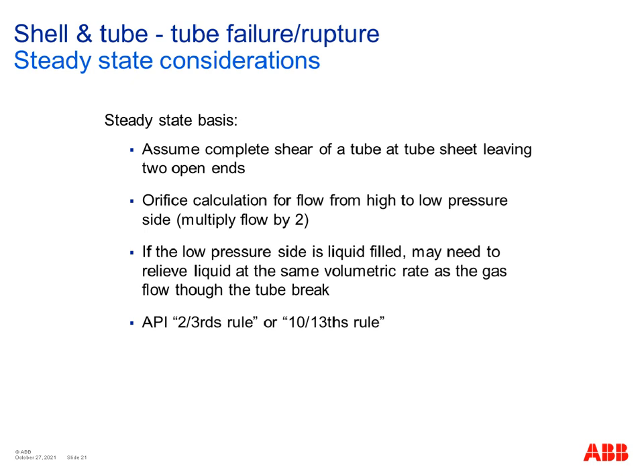So you've got a stub at the tube sheet, and then you've got flow coming out from that, and then you've also got the end of the tube that's broken from the tube sheet connection. So you've also got the flow coming through from that. So you work out the flow through one of the orifices based on the size of the tubes, and then you multiply that by 2 to get your flow that's going to come through in that event.